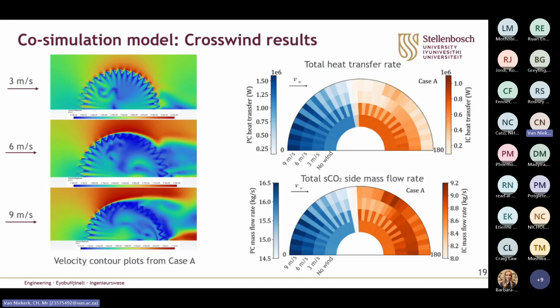So now we can just look at some of the crosswind results. So we know that crosswinds significantly deteriorate the heat rejection capability of the cooling tower. And this is effectively just illustrated by the formation of flow separation and flow stagnation in these middle and leeward sectors of the tube banks, which is increasingly severe for the high wind velocity cases. This reduces the overall air mass flow rate that can pass through these tube banks, which reduces the heat transfer. And we can use the co-simulation model to investigate the heat rejection rates of each individual heat exchanger tube bank with the use of a heat map.